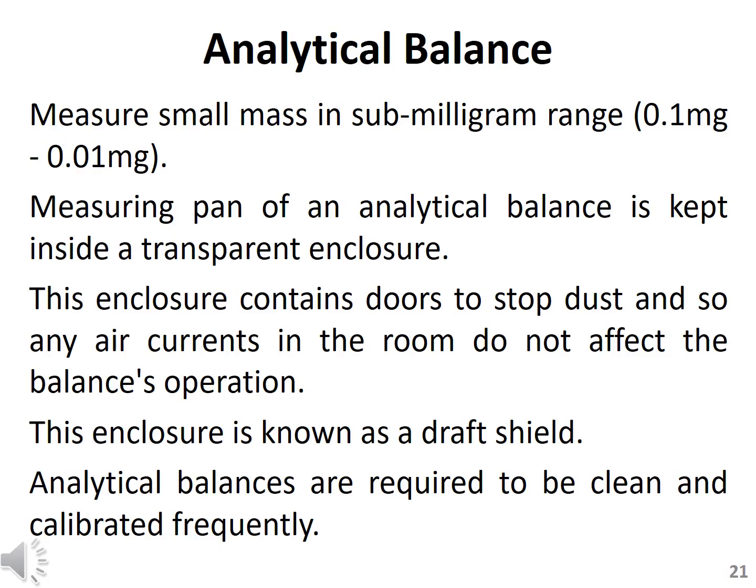So this analytical balance contains a measuring pan which is kept inside a transparent enclosure, because this enclosure contains a door to stop or inhibit the movement of dust particles and air current into the pan of the analytical balance. This enclosure is usually called a draft shield. Analytical balances are required to be monitored and cleaned very carefully and calibrated frequently.